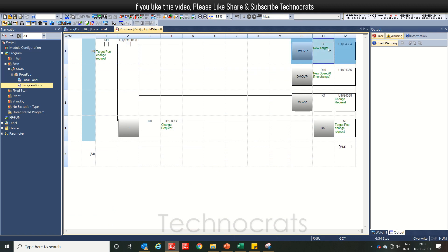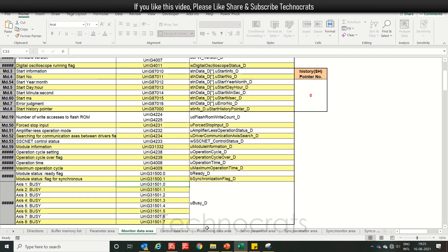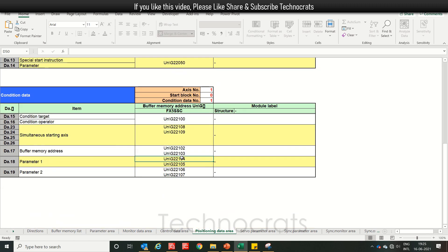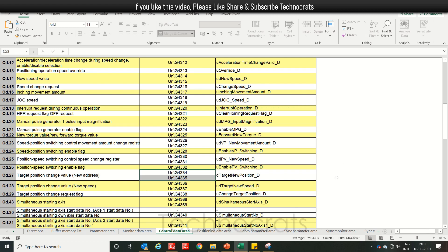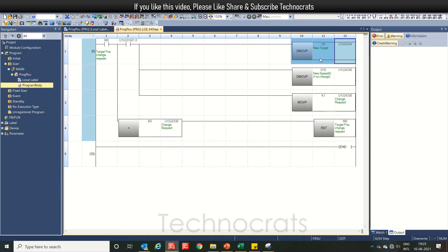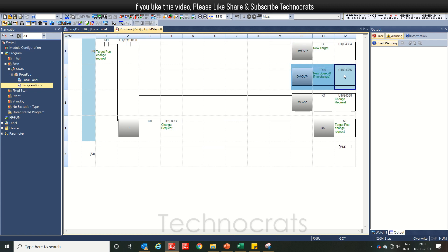The new target position is D0, mapped to U1-G 4334. D10 is your new change speed. Note: if you use zero here for the speed, there will be no change in speed — only the target position will change.